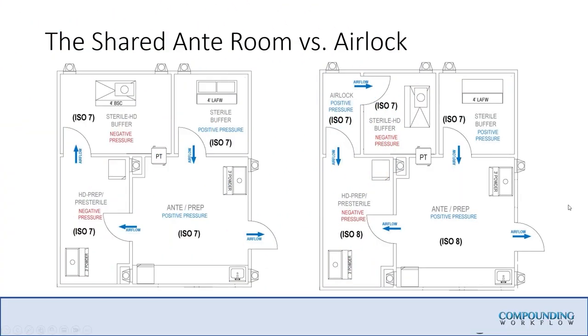Here is the shared anteroom versus the airlock — let's call this design criteria A. If you notice, all of these rooms share air. So my anteroom, with the line of demarcation here, is where I'm doing everything non-hazardous prep and hand hygiene. It shares air going into the HD prep, which would be high risk — like testosterone injectables. So I'm going from non-sterile to sterile, pulling air in here and that same air gets pulled into the sterile HD buffer. In this example, all of these rooms are essentially sharing air, which means the entire clean room needs to be rated as ISO 7.